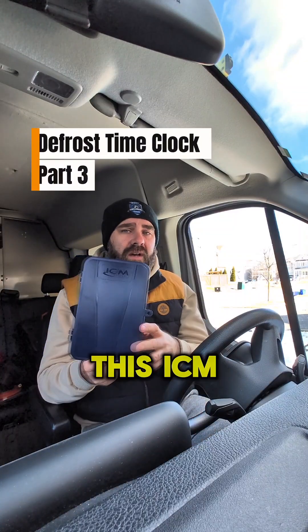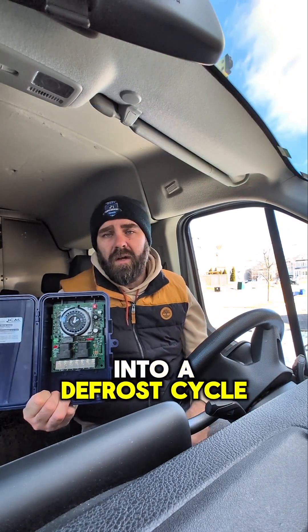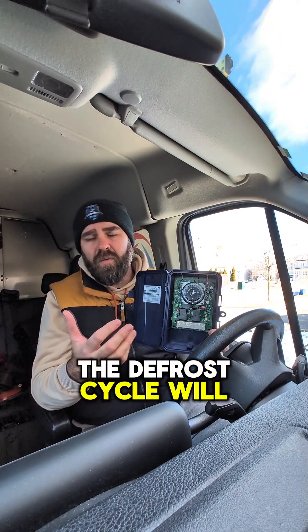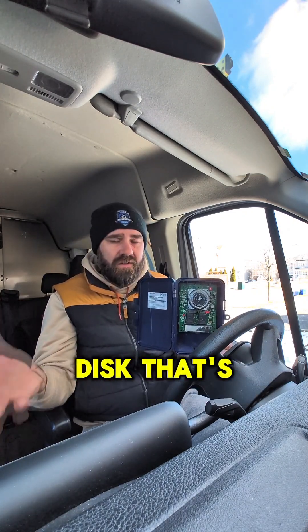Here's part three on this ICM defrost clock. In the first two videos we covered defrost termination, then we covered what happens when we go into a defrost cycle. What happens when we come out of a defrost cycle? That is probably the easiest part of this. The defrost cycle will either terminate by time on the clock — as we've set it here for 45 minutes — or will come out on defrost termination by a temperature switch, like a Klixon disc mounted on the evaporator coil itself.